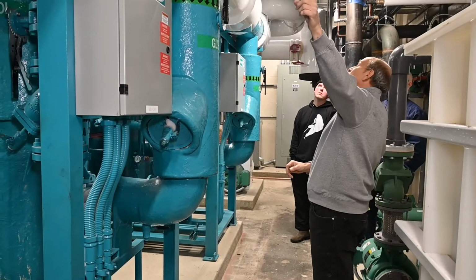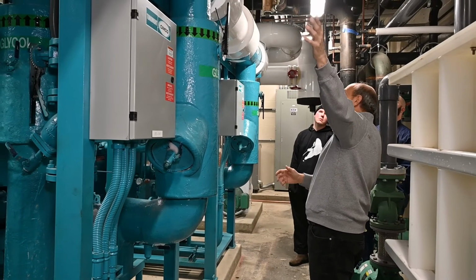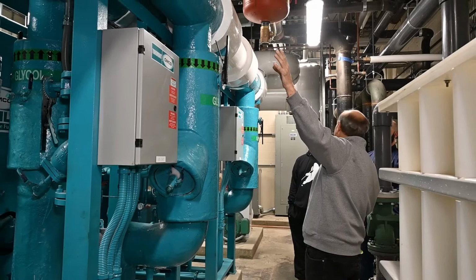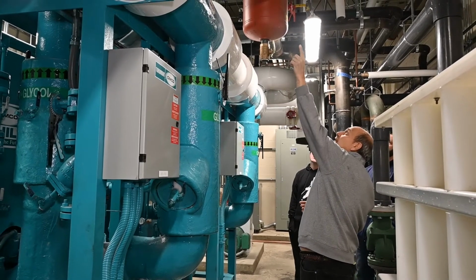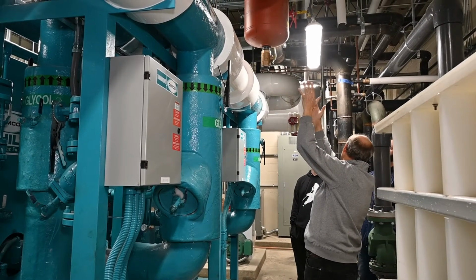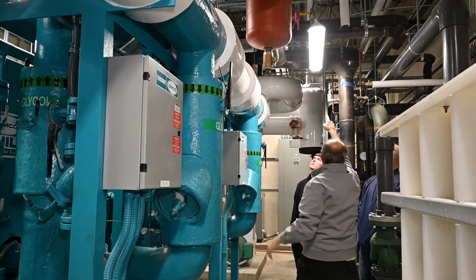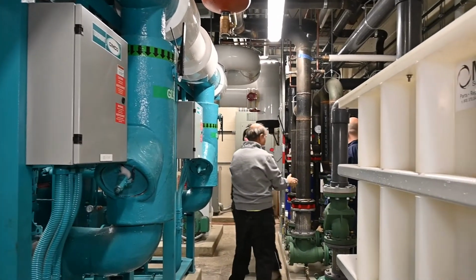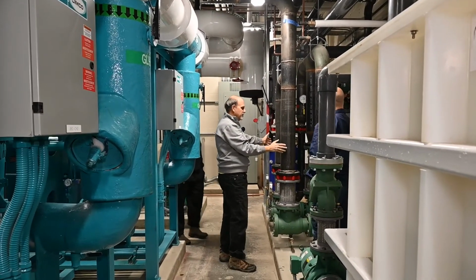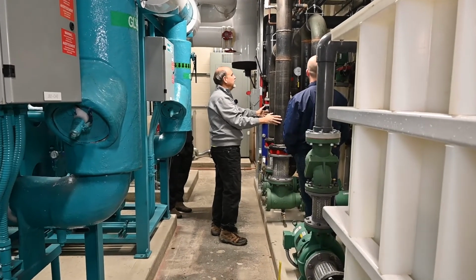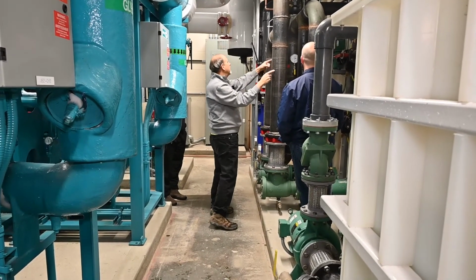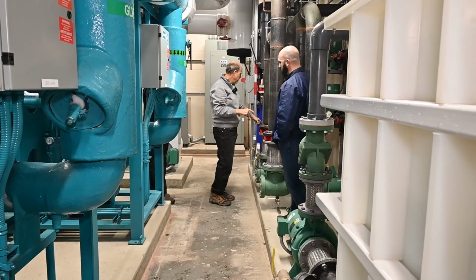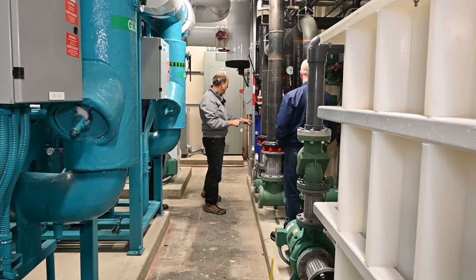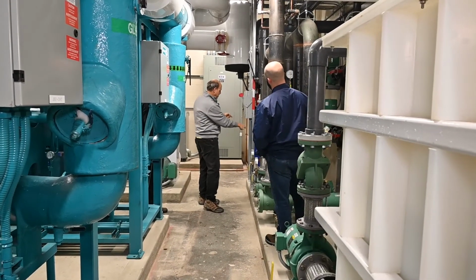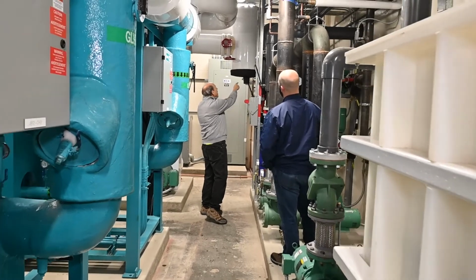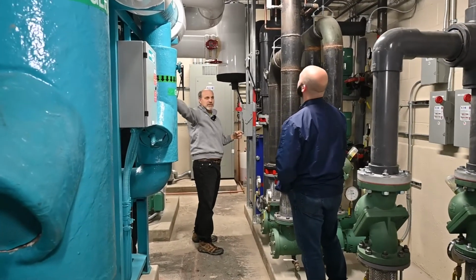So the way that system runs is the hot glycol coming out of the chillers that needs to be cooled, coming out on this pipe right here, goes through another air separator to purge the air out, comes this way, comes down into pumps P3 and P4, which is your warm loop glycol pumps, and basically pumps up. It goes through your heat exchanger, and that is the heat exchanger to go through and back up, and it just loops back to the chillers.